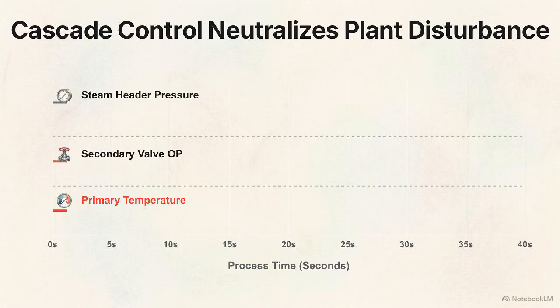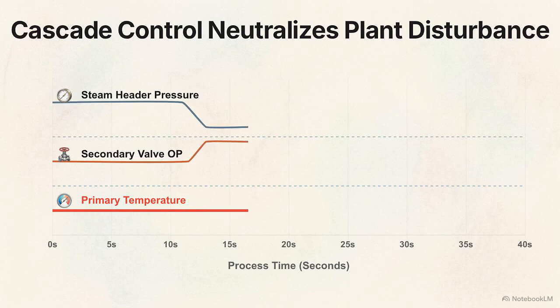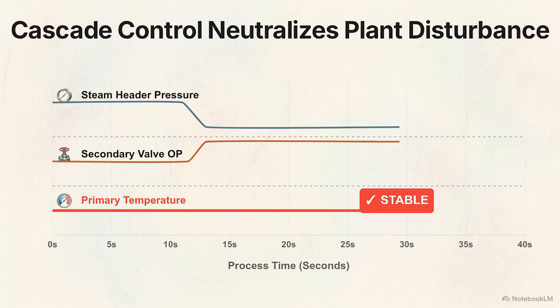Let's put our completed heat exchanger system to the test. This chart shows our process running perfectly at steady state across 3 variables. Watch what happens when that massive plant steam pressure drop hits us again. The pressure drops sharply. In a fraction of a second, the secondary flow sensor detects the loss of steam volume. The inner flow controller immediately spikes its output, driving the valve wider to maintain the required steam flow before the heat exchanger ever loses thermal energy. Look at the primary product temperature. It stays perfectly flat.